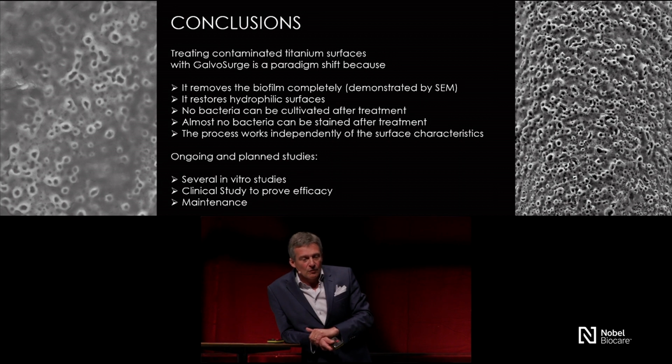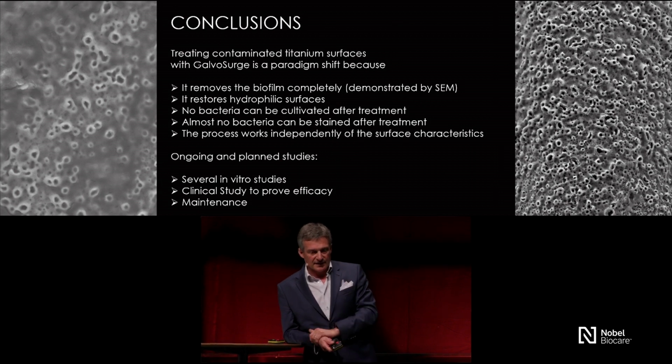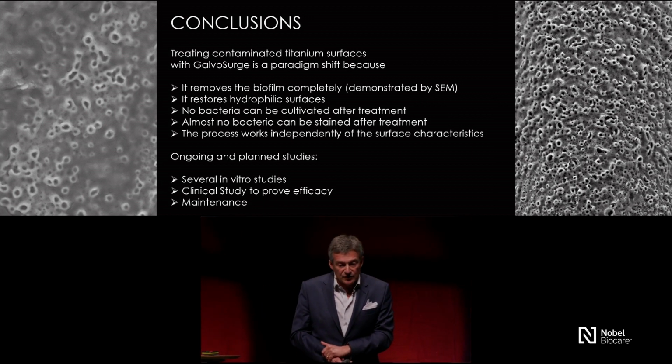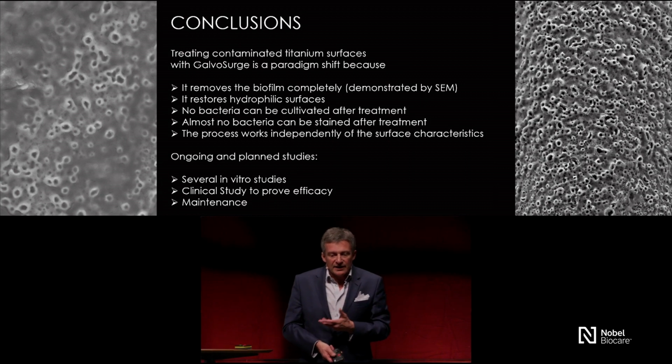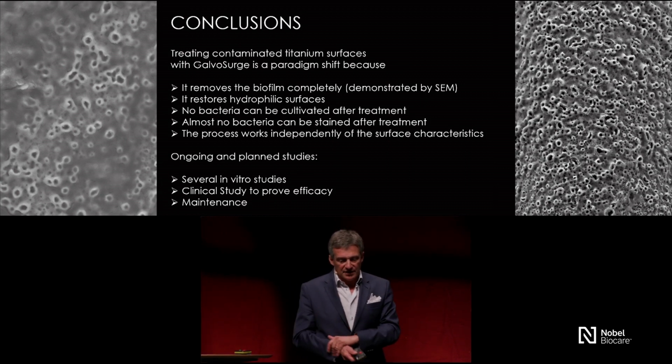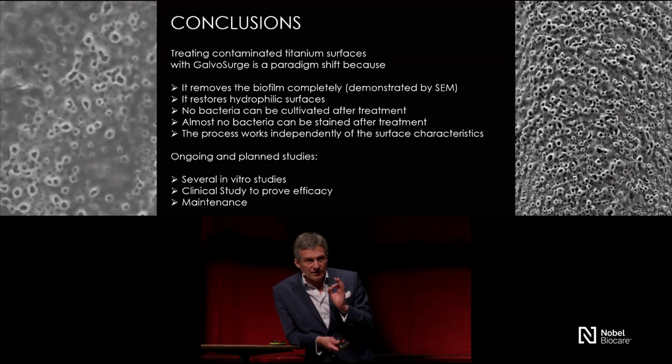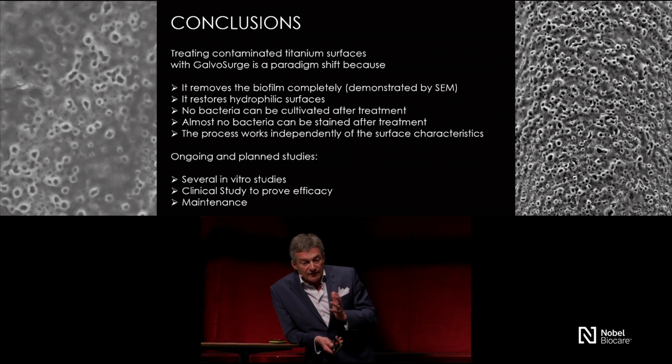Conclusions. What can we prove or claim today? We demonstrated by SEM that we are able to remove the biofilm completely with all the limitations of these techniques. We can, I didn't talk about that, but we can regain hydrophilic surfaces. We can cultivate no bacteria, and we cannot stain bacteria. And this process works independently of surface characteristics and manufacturer. Ongoing are several in vitro studies and, of course, a multi-center study.